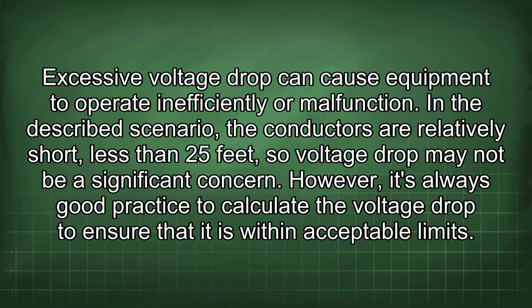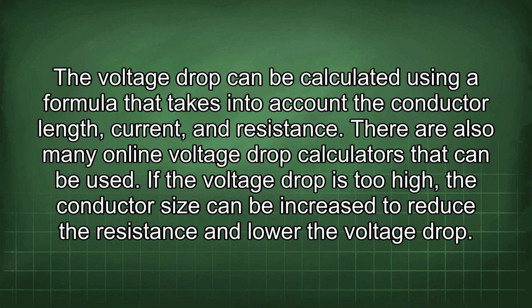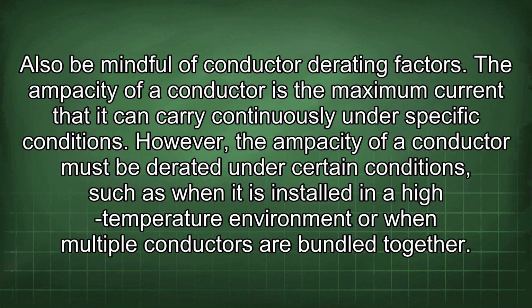In the described scenario, the conductors are relatively short, less than 25 feet, so voltage drop may not be a significant concern. However, it's always good practice to calculate the voltage drop to ensure that it is within acceptable limits. The voltage drop can be calculated using a formula that takes into account the conductor length, current, and resistance. There are also many online voltage drop calculators that can be used. If the voltage drop is too high, the conductor size can be increased to reduce the resistance and lower the voltage drop. Also be mindful of conductor derating factors.